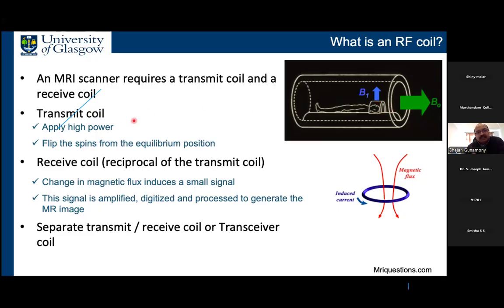So there is a transmit coil. We apply high power on the transmit coil, and this will then flip the spins from the equilibrium position. So this is the function of the transmit coil. A receive coil is exactly reciprocal to the transmit coil. It works on the principle of Faraday's laws of induction. So basically, we have the spins that are precessing in the magnetic field. So we have this oscillating magnetic field which induces a current in a neighboring conductor. In this case, this neighboring conductor is the receive coil, and the signal induced in this receive coil is the MR signal, which we then amplify, digitize and process, and then we get the MR image. So we typically use a separate transmit coil and separate receive coil.